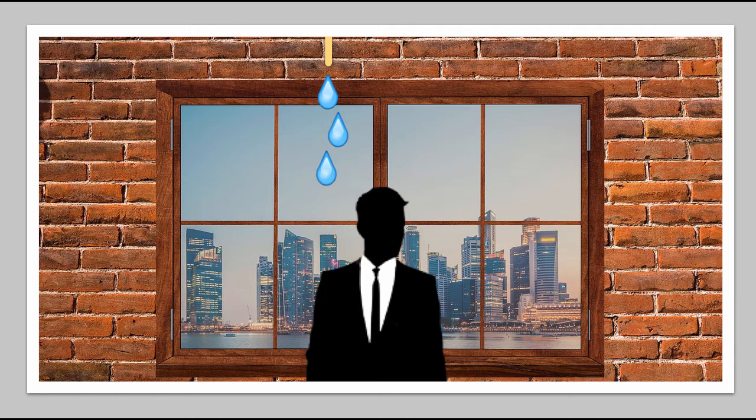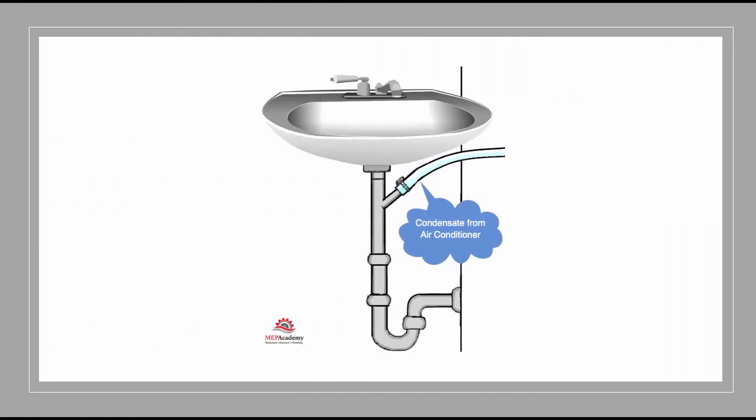On your primary drain terminations, you have options where you can terminate them as indirect drains. If you have a condensate pump, you can pump that to an indirect drain. You can also terminate in dry wells, leach pits, landscaped areas that are properly designed to handle the volume of condensate, and properly designed stormwater treatment systems. Check with your local code to see which of these is acceptable in your area.